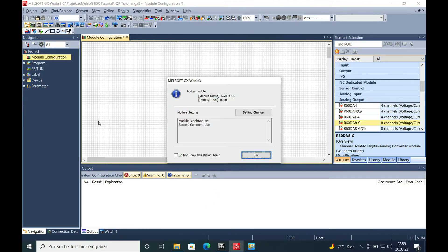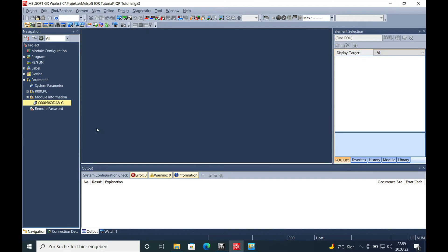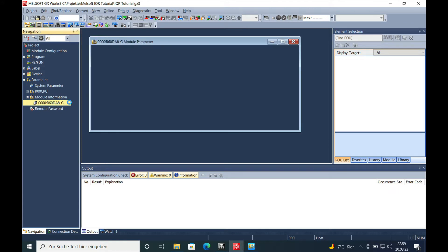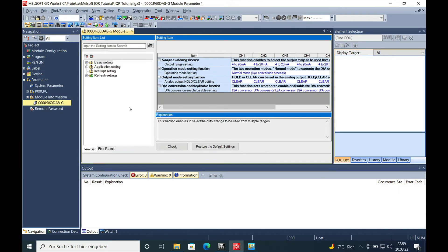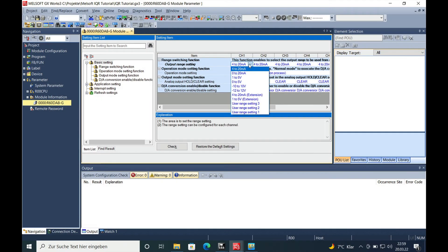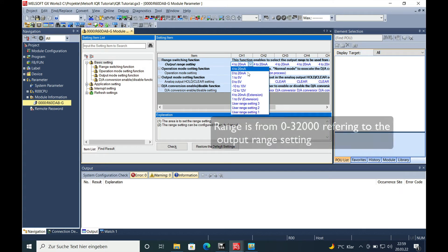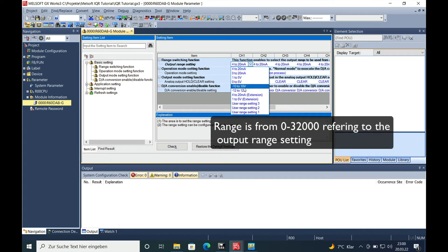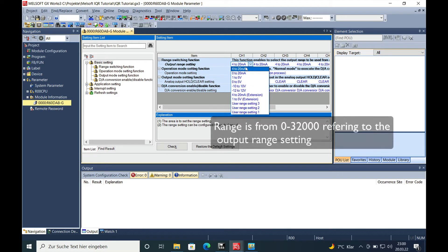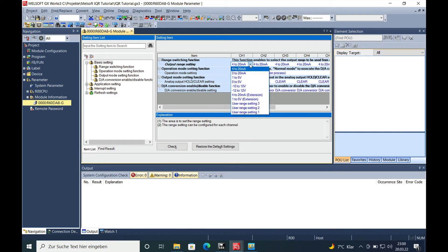And then you will see a new module is being added and the parameter, the module information for this module appears right here. If you make a double click on here you can see your basic settings, you can see your output range where you can choose anywhere from 4 to 20mA, minus 10 to plus 10V, anything you basically need.